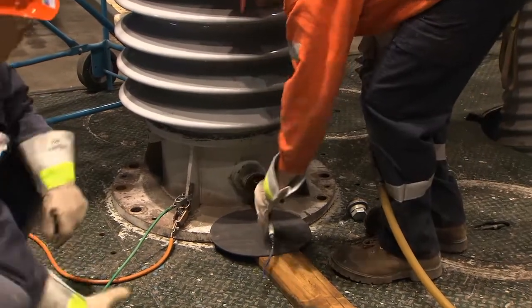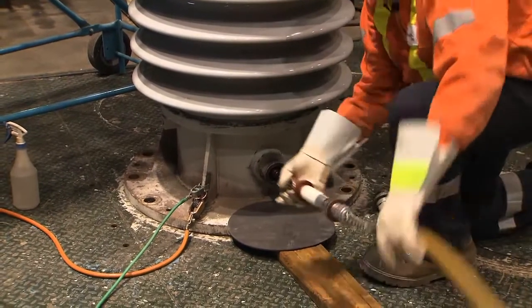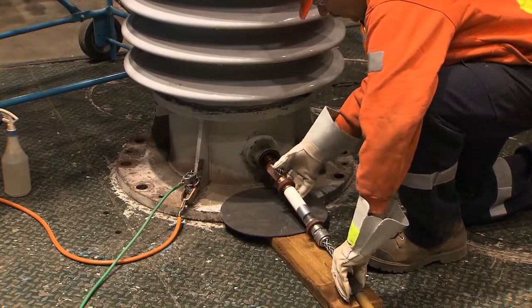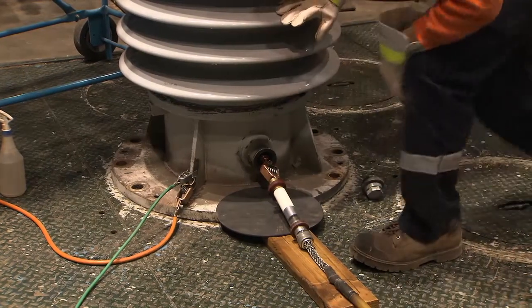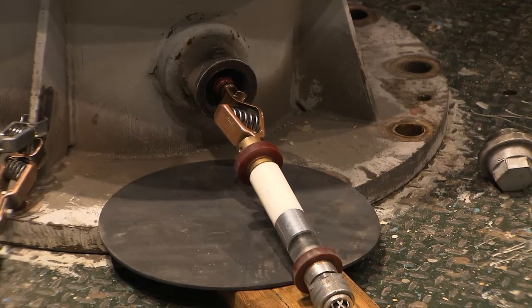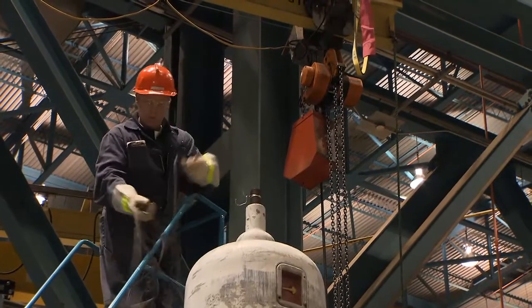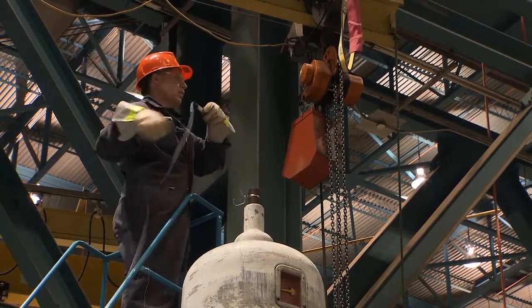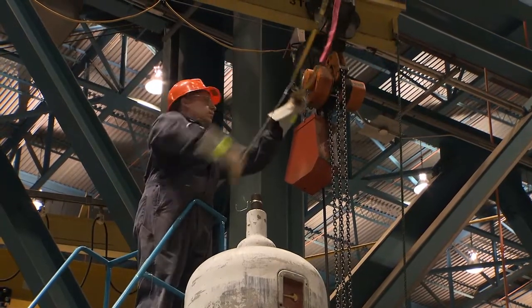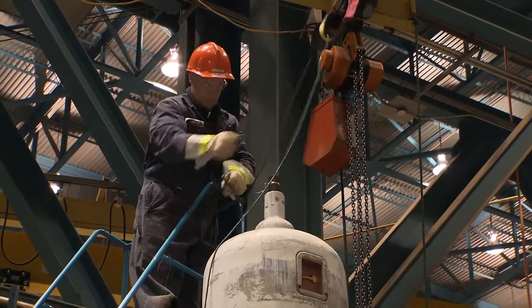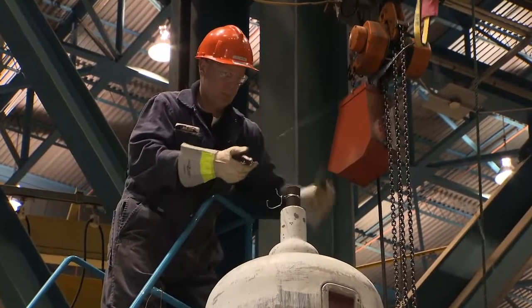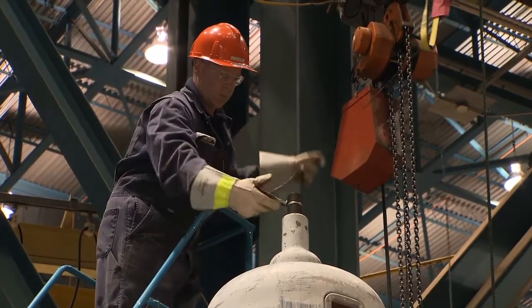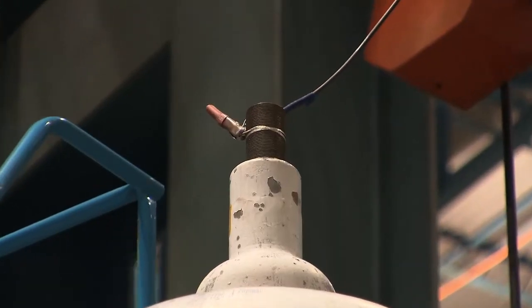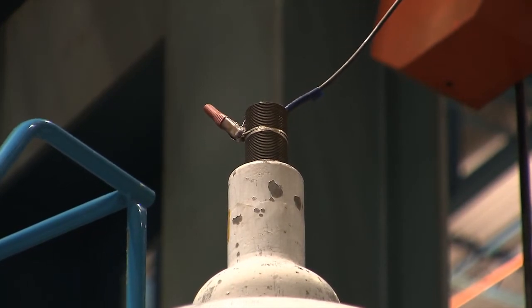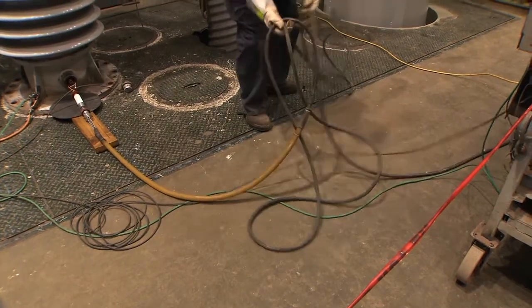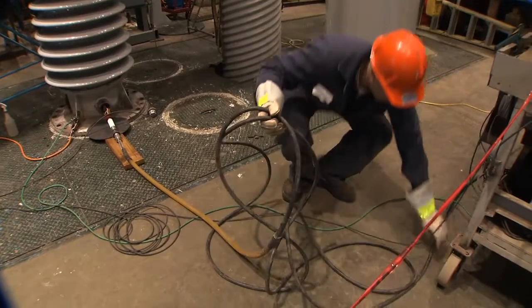Disconnect the low voltage lead from the capacitance tap and reconnect the high voltage lead in its place. Connect the low voltage lead to the pure copper strand at the top of the conductor core and support the cable using a sling suspended from the hoist hook above. Unravel the wires on the floor from each other to prevent stray current from interfering with the test.